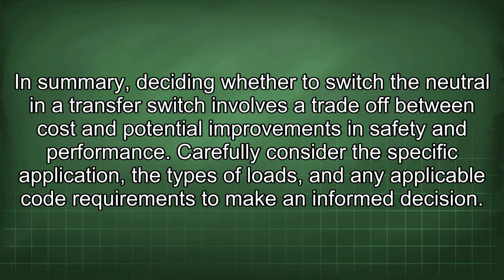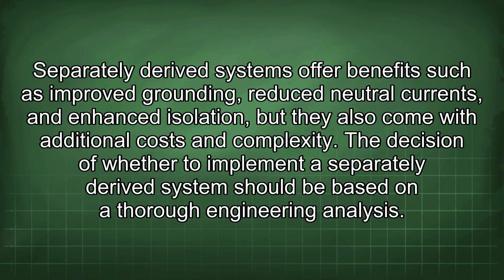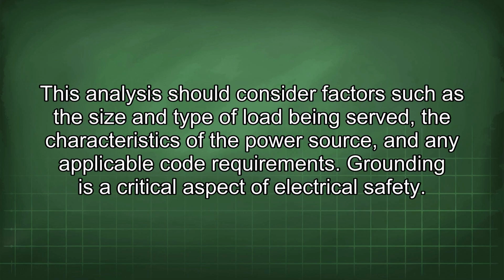Separately derived systems offer benefits such as improved grounding, reduced neutral currents, and enhanced isolation, but they also come with additional costs and complexity. The decision of whether to implement a separately derived system should be based on a thorough engineering analysis. This analysis should consider factors such as the size and type of load being served, the characteristics of the power source, and any applicable code requirements.